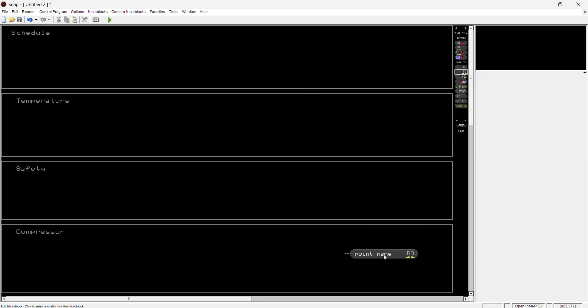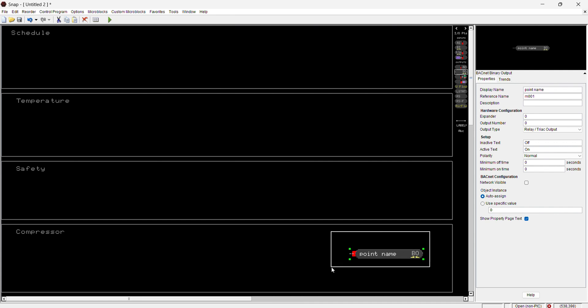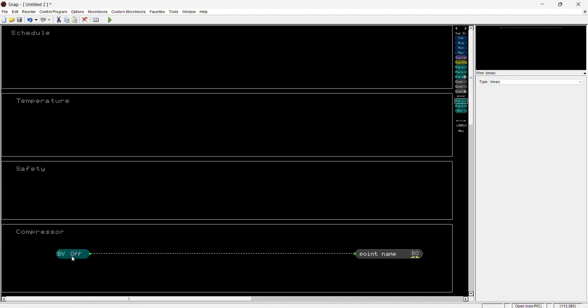By putting in this binary output, you can think of this as a contactor coil or relay coil. In a previous video I went over binary outputs and the contactor coil — I showed how that contactor coil has the common wire already present. All I'm doing is deciding when that 24 volts goes to the other side of that coil. With the binary output, you have 24 volts, and when I activate binary output one it connects a little bridge between the power and the binary output, sending 24 volts to my contactor coil.